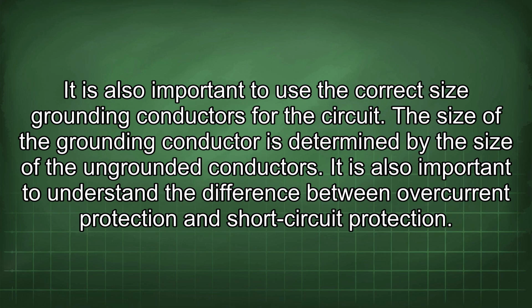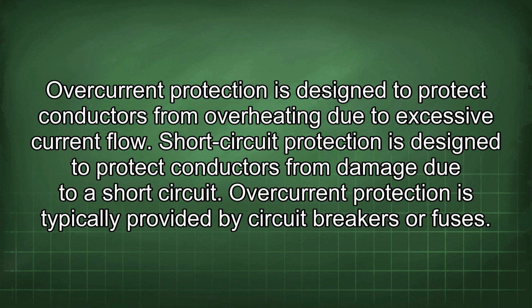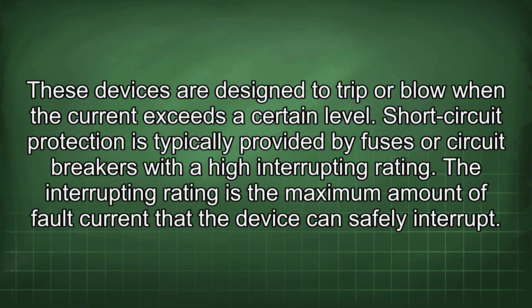It is also important to understand the difference between overcurrent protection and short-circuit protection. Overcurrent protection is designed to protect conductors from overheating due to excessive current flow. Short-circuit protection is designed to protect conductors from damage due to a short circuit. Overcurrent protection is typically provided by circuit breakers or fuses. These devices are designed to trip or blow when the current exceeds a certain level. Short-circuit protection is typically provided by fuses or circuit breakers with a high interrupting rating. The interrupting rating is the maximum amount of fault current that the device can safely interrupt.